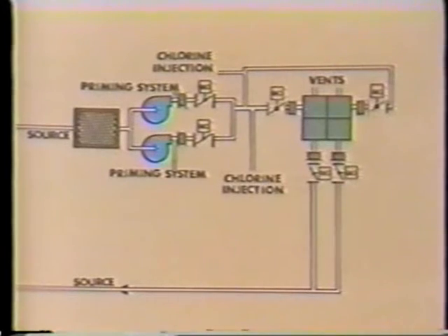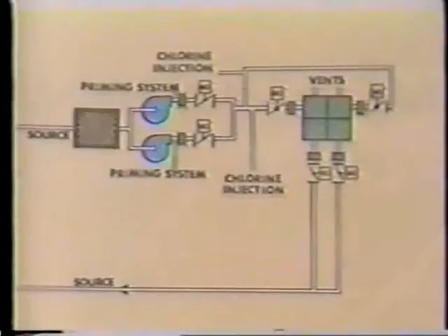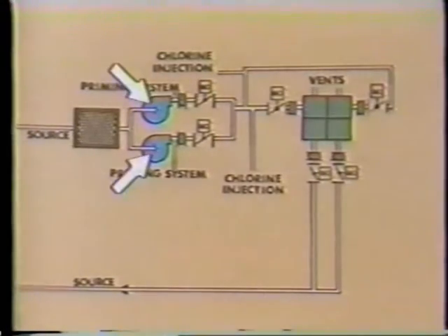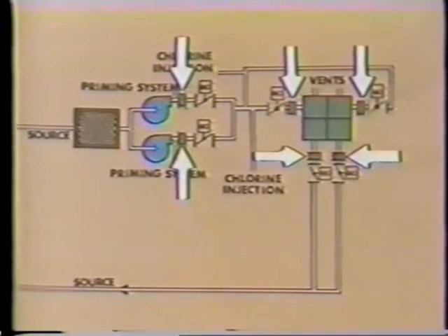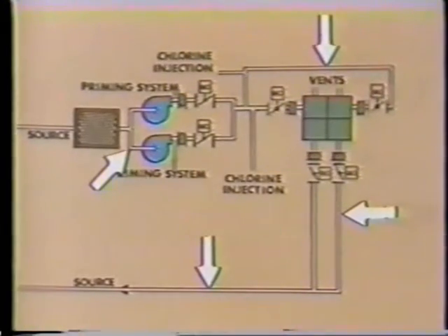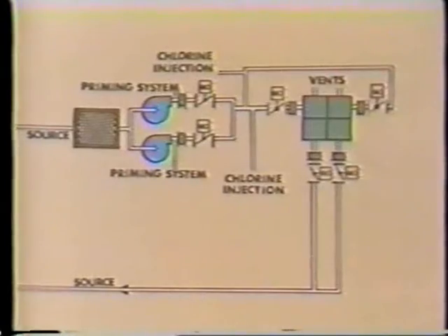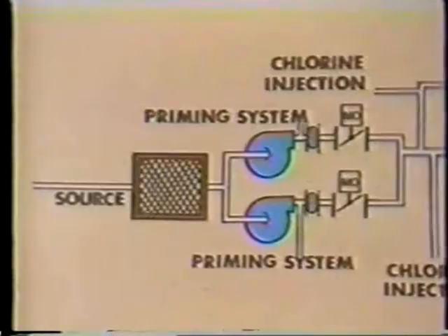This simplified drawing represents a typical circulating water system. This type of system is often referred to as a once-through system because water is returned to its source after flowing through the condenser once. This system is often used where the water source is large, such as a river, a lake, or ocean. And as you can see on this drawing, the system consists of screens, pumps, valves, expansion joints, and piping. Let's follow the flow of circulating water from the water source and through this system.